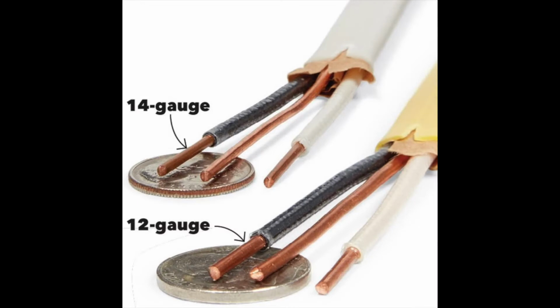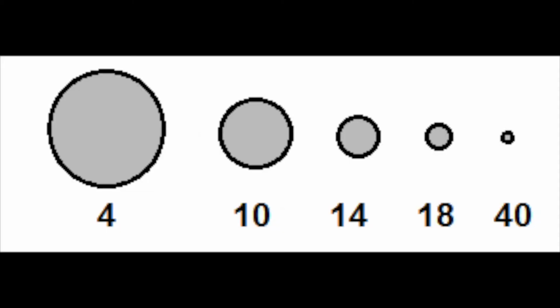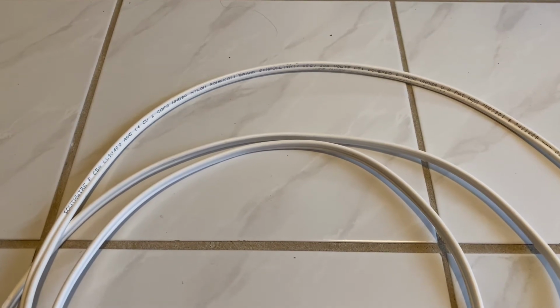Wire gauges. Here's a comparison between a cable with 14 gauge wires and 12 gauge wires. The 12 gauge wires are slightly thicker in diameter. Wires range from 40, a very thin wire, to 0, a very thick wire. There are even thicker wires too, like 00, 000, and more. In homes, we typically see 14, 12, and 10 gauge wires. Generally speaking, the thicker the diameter of the wire, the smaller the gauge number. 14 gauge is used in most of the circuits in our homes. Amps. Amps are a measure of electricity or current. The bigger the number, the more electricity and electrical devices can be supported on a circuit.